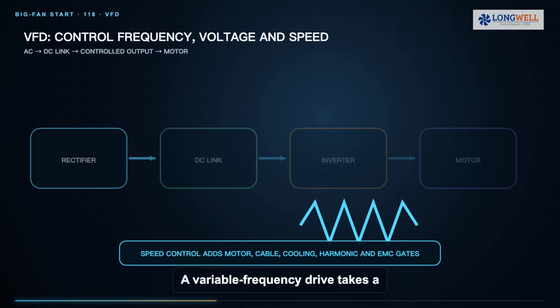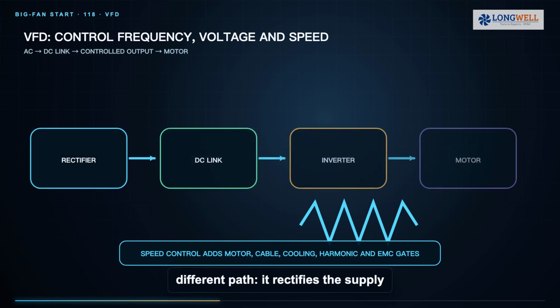A variable frequency drive takes a different path. It rectifies the supply to a DC link and synthesizes controlled output frequency and voltage. It can coordinate motor flux and acceleration, limit the supply-side start event, and continue regulating fan speed after startup. That extra capability also adds motor compatibility, cable, cooling, harmonic, EMC, and commissioning requirements.